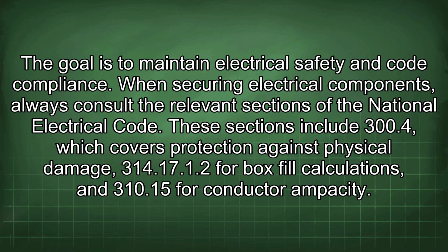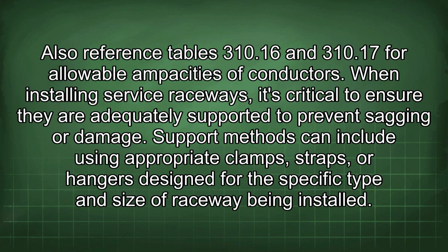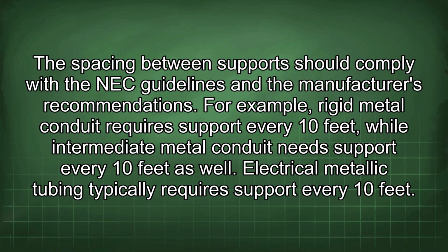When securing electrical components, always consult the relevant sections of the National Electrical Code. These sections include 300.4, which covers protection against physical damage, 314.17 1.2 for box fill calculations, and 310.15 for conductor ampacity. Also reference tables 310.16 and 310.17 for allowable ampacities of conductors. When installing service raceways, it's critical to ensure they are adequately supported to prevent sagging or damage. Support methods can include using appropriate clamps, straps, or hangers designed for the specific type and size of raceway being installed. The spacing between supports should comply with the NEC guidelines and the manufacturer's recommendations.